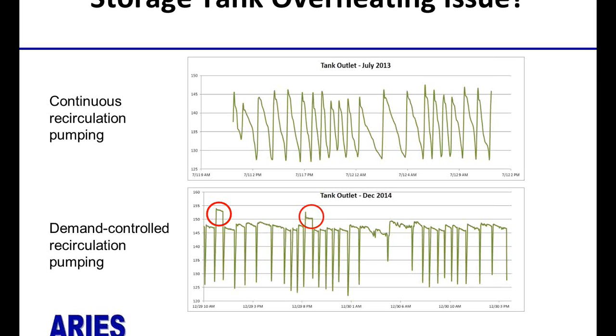Another possible issue that was presented to us is this idea that with a storage tank and demand recirculation controls installed, you can potentially send very hot water at irregular intervals to the supply pipes. So the top graph, these are both from the same building. These are both supply temperatures coming from the tank. You see this signature sawtooth pattern, and that's characteristic of the tank water being mixed by the recirculation pump that's operating continuously. So you can see it steadily declines as more and more makeup water is added before the boiler fires. And in the bottom graph, this is what you'd find with either no recirculation system in place at all or with the demand controls that are running the pumps very infrequently. You get more of a flat plateau.